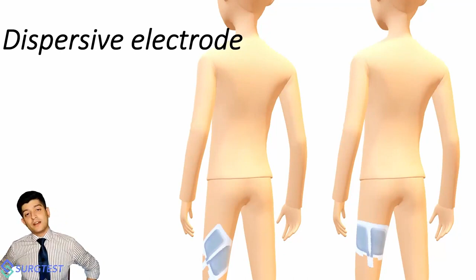Another common issue with the dispersive electrode is the orientation in which it is placed on the patient. Sometimes you will have it placed obliquely, as a result of which a corner is towards the side that you're sitting and operating. So most of the energy that returns by means of the dispersive electrode gets concentrated at this leading corner that is present over here. And because most of the electrical energy is coming in by the path of least resistance at this corner, you will end up developing a small burn at this area.